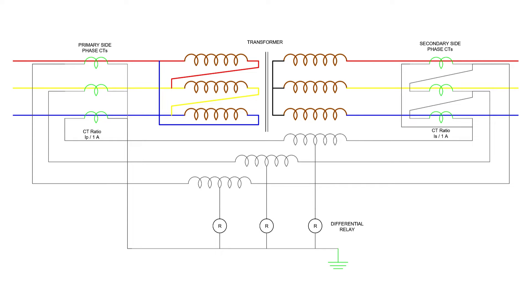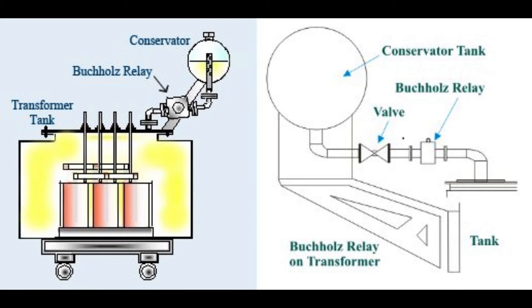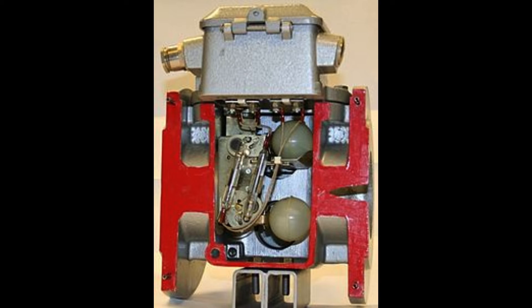The differential protection of a transformer has many advantages over other protection schemes. Faults occurring inside the transformer within the insulating oil can be detected by a Buchholz relay, but if any fault occurs in the transformer but not in the oil, it cannot be detected by the Buchholz relay. Any flashover at the bushings is also not adequately covered by the Buchholz relay. Differential relays can detect such types of faults. Moreover, while the Buchholz relay detects internal faults, the differential protection scheme detects them in a much faster way.